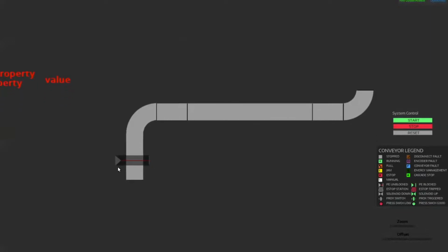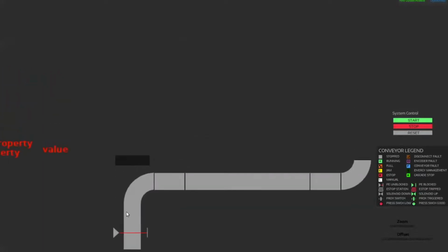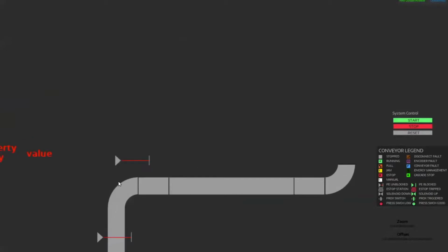Let's say there's a full photo eye. Now Jack, you might not be as aware, but for the photo eyes, one thing that is consistent is pretty much every single conveyor has an exit photo eye, because we track the packages through the system, and we can track whether a box is on this conveyor or that conveyor by knowing when it's crossed that exit photo eye.